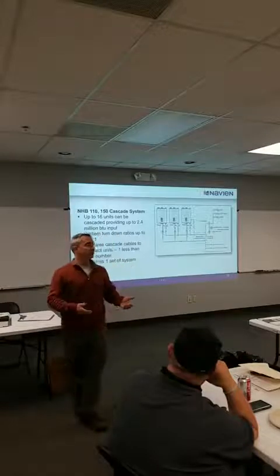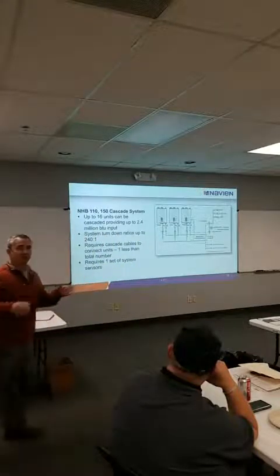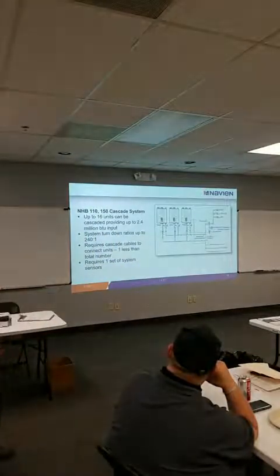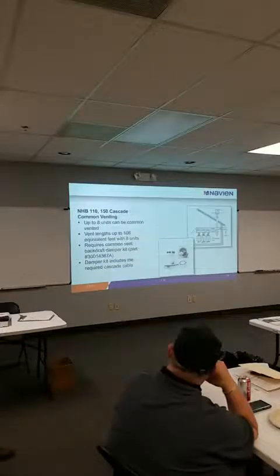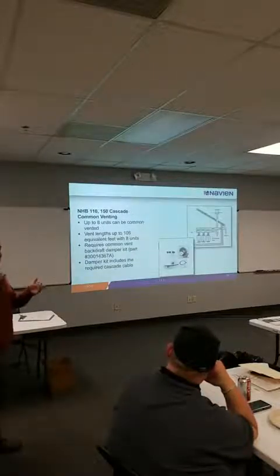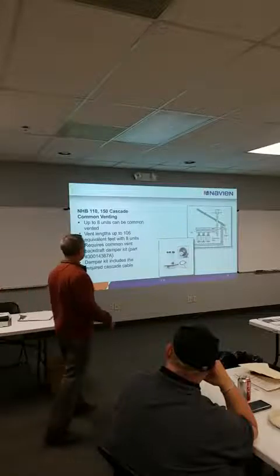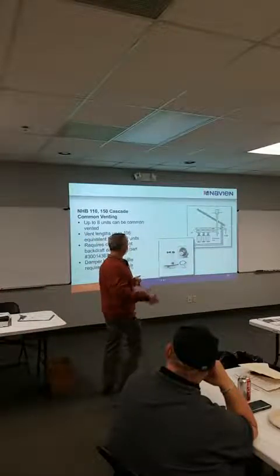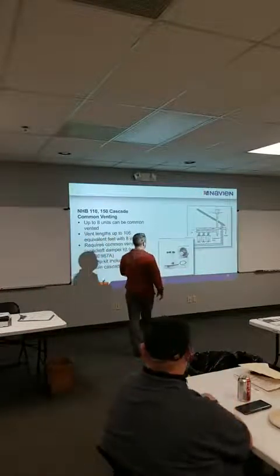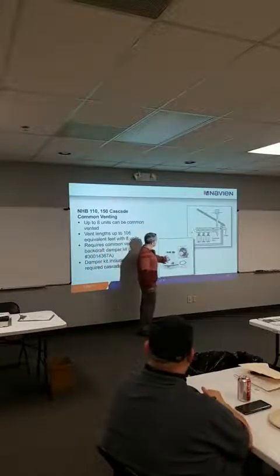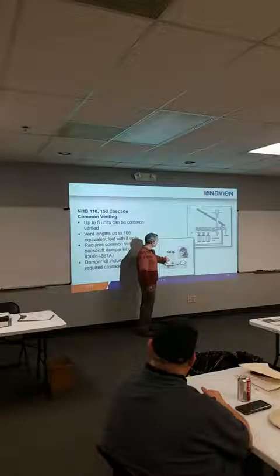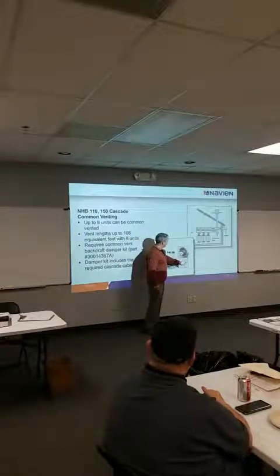You can do individual primary, secondary, you can do a common primary, secondary, where you're going in the headers and setting the system up. So we have cascade cable that goes between the systems, that sets up your primary unit and all your secondary units. But when you go to multiple units, you do have to purchase this vent damper kit. I think they're like $30. It comes with the communication cable.